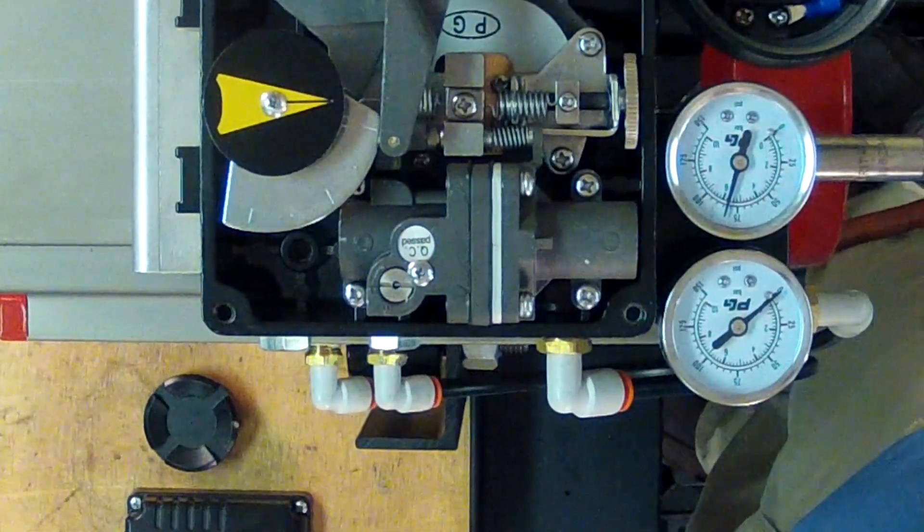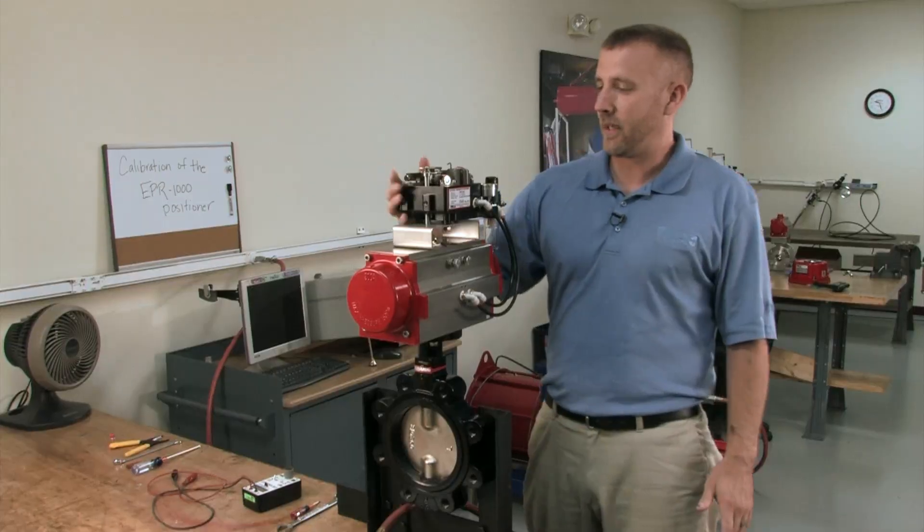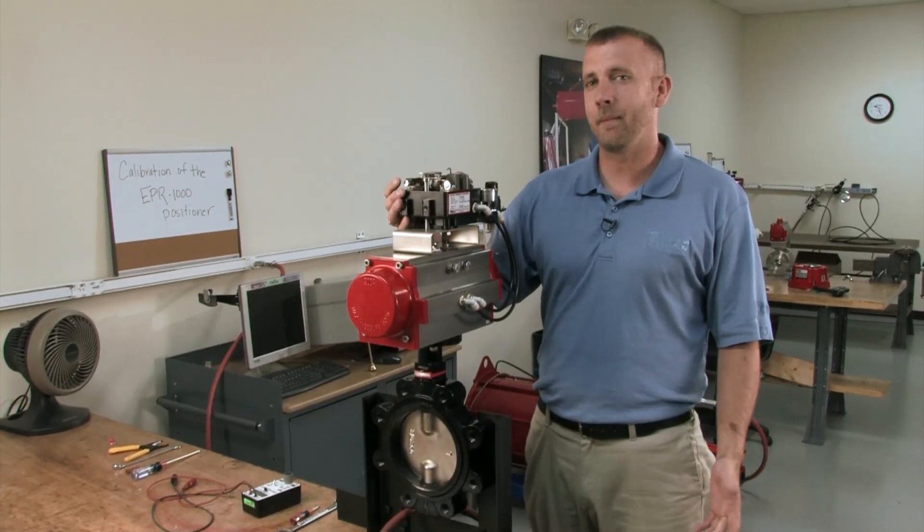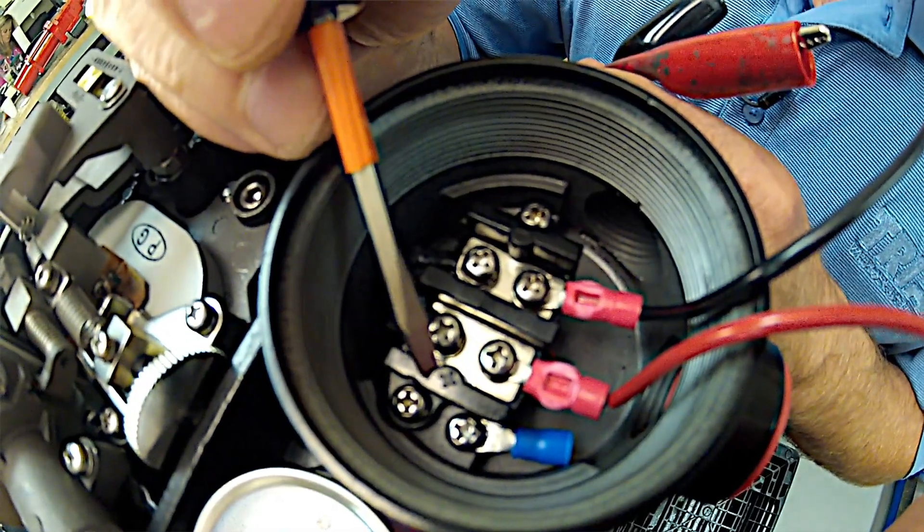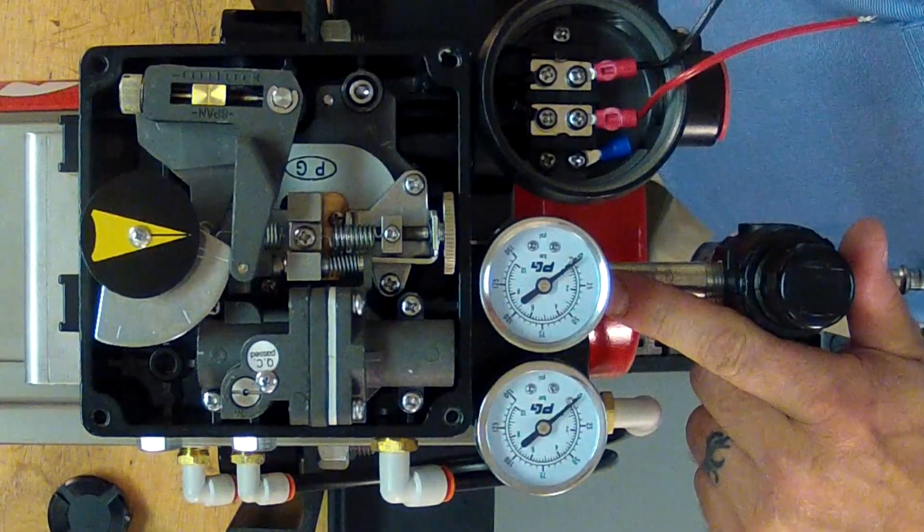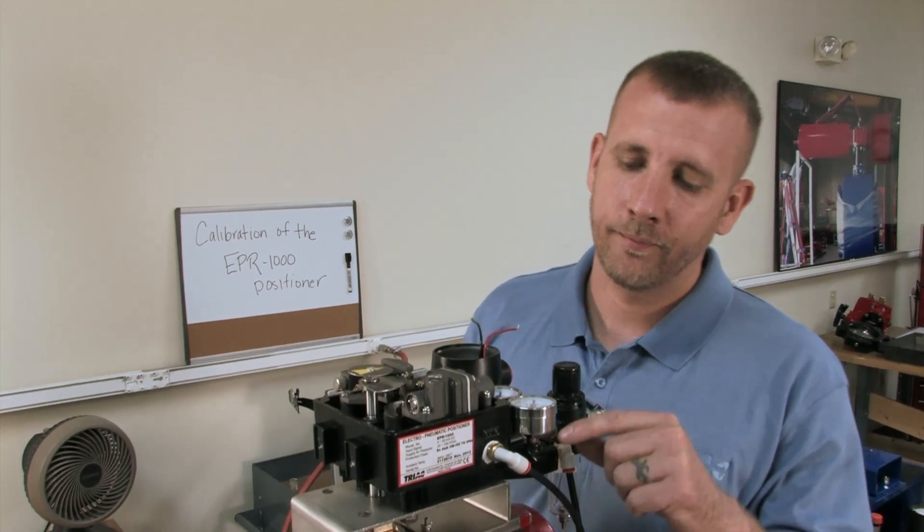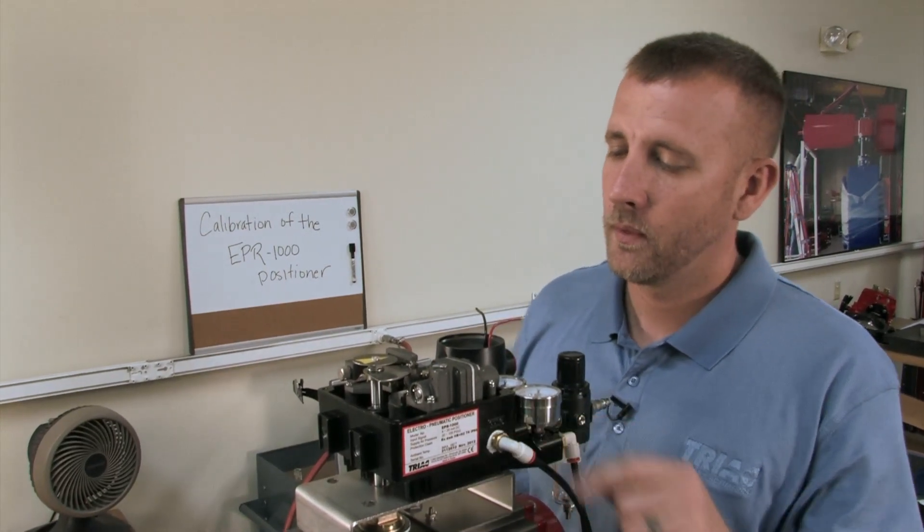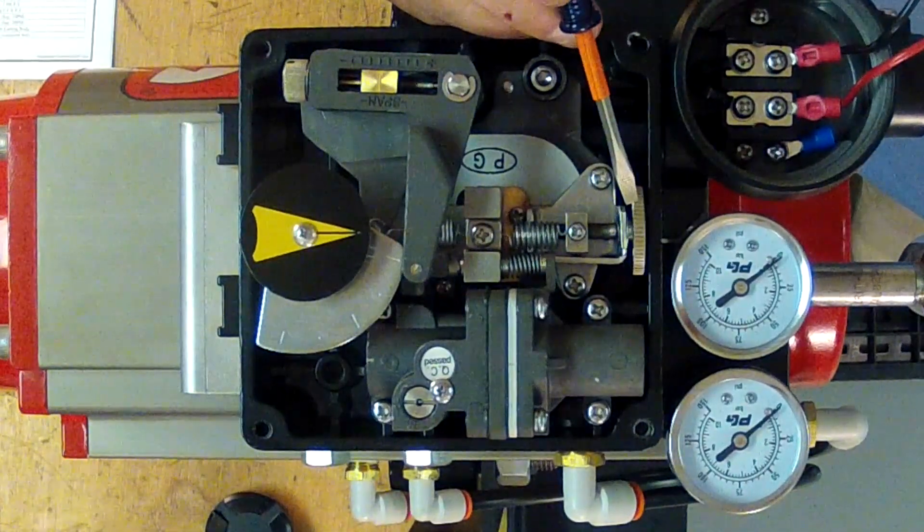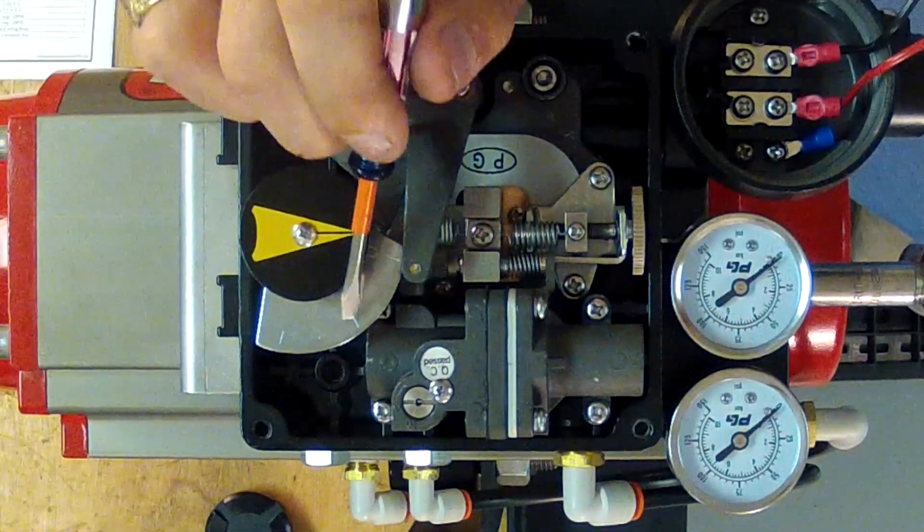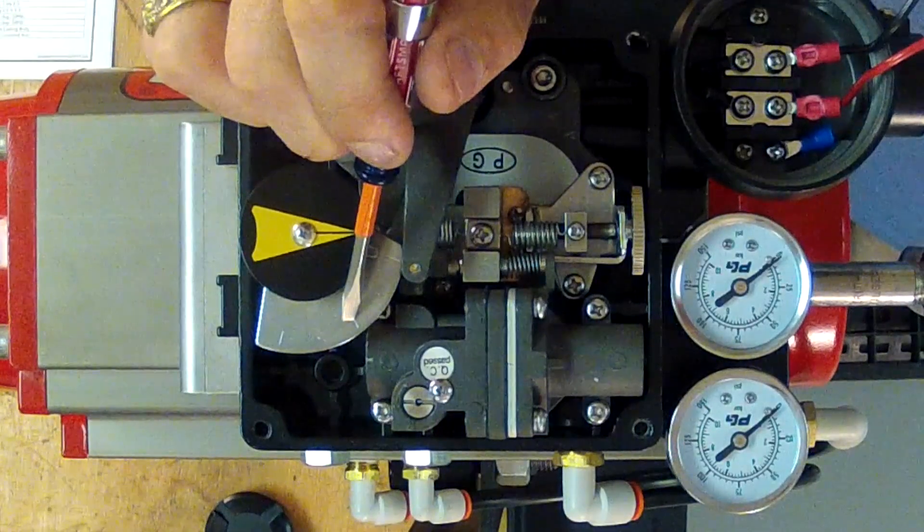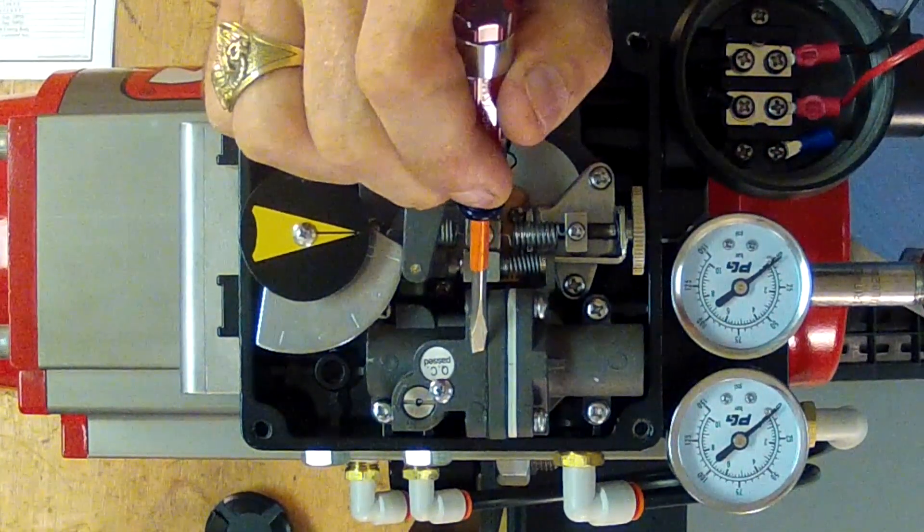Now, we're going to do the basic calibration of the positioner. This is our basic EPR-1000, four to 20 milliamp DC control voltage positioner. Your electrical connection, positive and negative, air supply connection, your out one, out two, zero adjustment screw, span adjustment screw, travel cam, and your pilot valve.